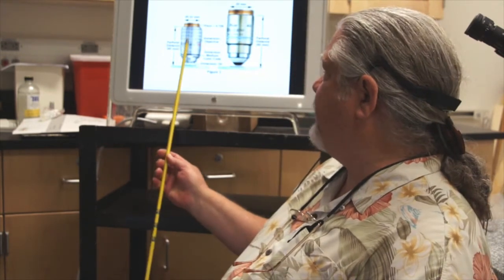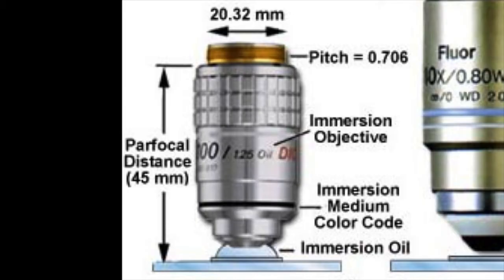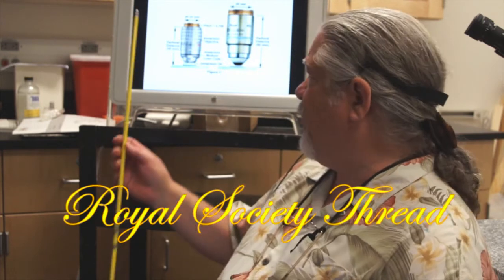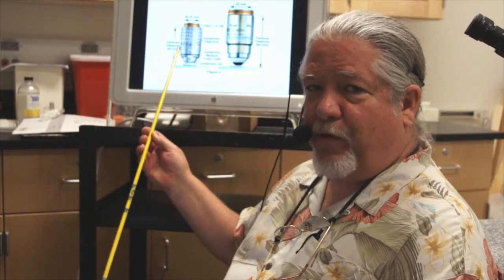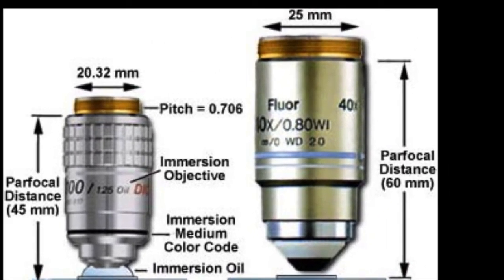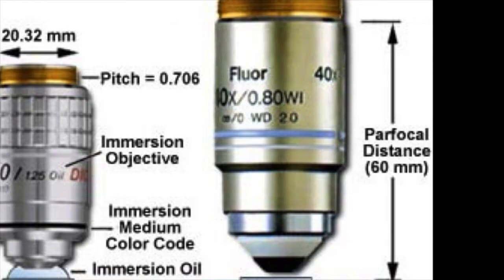There are other things important about interchangeability of objectives from microscope to microscope. Here you see two different size objectives. One is an old-style fixed tube length or 160-millimeter tube length objective with a smaller thread. This has a 20.32-millimeter thread, called the Royal Society thread. For about 150 years, most microscopes employed this kind of objective. Manufacturers have changed and gone to bigger objectives with a larger thread. You cannot interchange a lot of objectives from older microscopes onto newer ones. Notice also the barrel length is much larger.